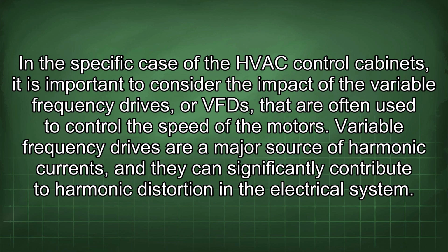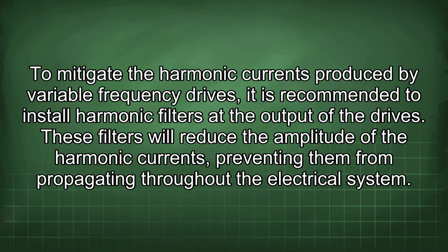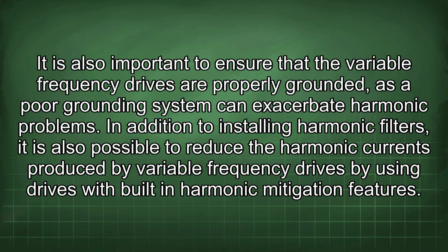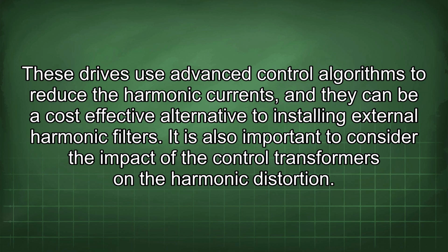Variable frequency drives are a major source of harmonic currents, and they can significantly contribute to harmonic distortion in the electrical system. To mitigate the harmonic currents produced by variable frequency drives, it is recommended to install harmonic filters at the output of the drives. These filters will reduce the amplitude of the harmonic currents, preventing them from propagating throughout the electrical system. It is also important to ensure that the variable frequency drives are properly grounded, as a poor grounding system can exacerbate harmonic problems. In addition to installing harmonic filters, it is also possible to reduce the harmonic currents produced by variable frequency drives by using drives with built-in harmonic mitigation features. These drives use advanced control algorithms to reduce the harmonic currents, and they can be a cost-effective alternative to installing external harmonic filters.